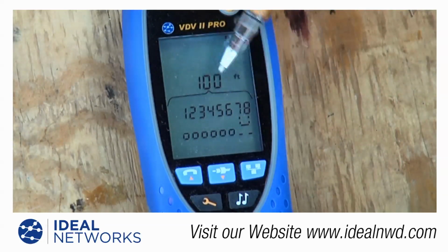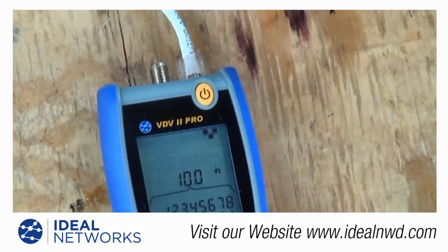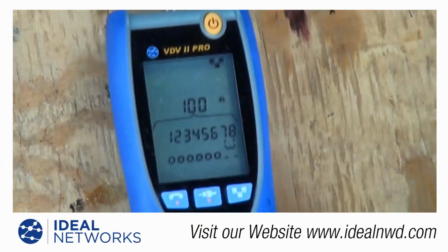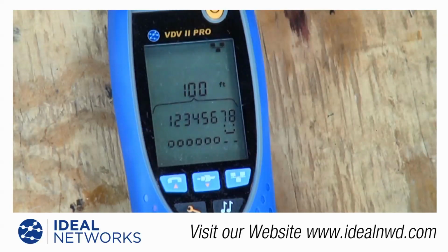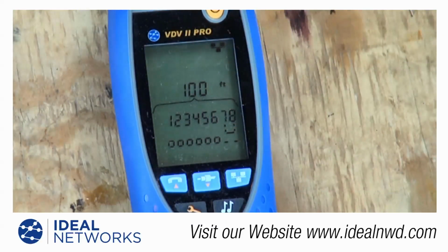So it's showing me about a 100-foot length of cable, with a cord plugged into the other end and really nothing connected there, and the tester is showing me all opens. The overall length we state in the specifications is about 1,500 feet, or about 450 meters.